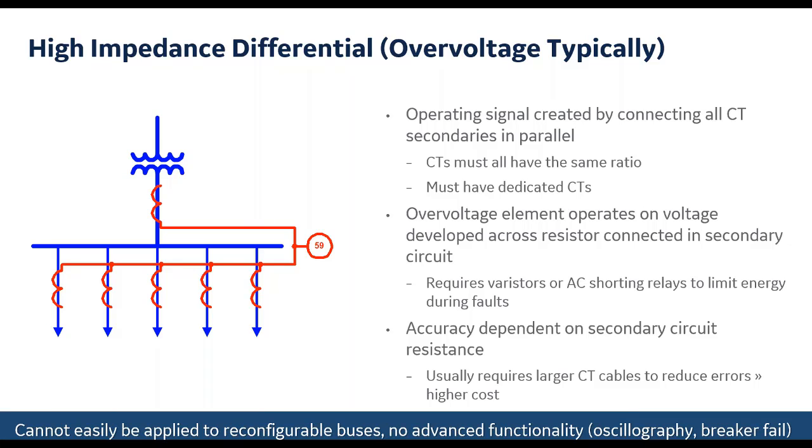Typically, the relay used is an overvoltage relay for some of the more legacy designs. But in most of today's designs, you can use an overcurrent relay, or really technically any overcurrent relay that has the sensitivity and the speed to be able to implement this scheme.